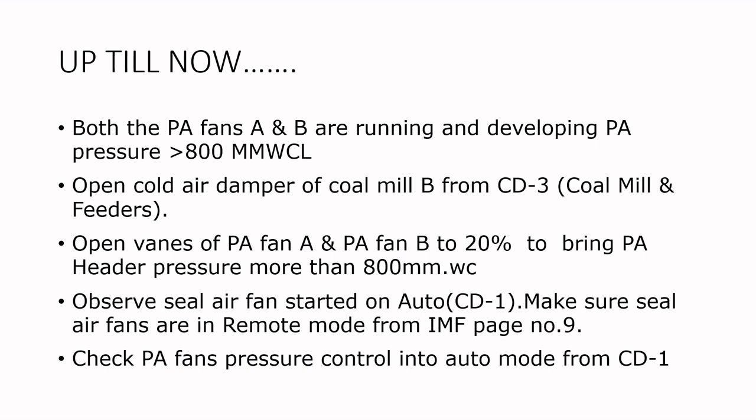Now open the vanes of PA fan A and B to around 20% to bring the PA header pressure more than 800. Now if you check last time we have done, the pressure was something around 1200 millimeters of water column. So it is already there, it should be more than 800 millimeters of water column.